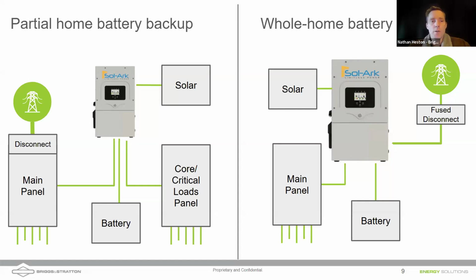So notice on the left side of the screen, if you disconnect from the grid, if you get a power outage, what's going to happen? Well, the inverter is going to isolate its power feed from the main panel, and you're going to essentially have just the battery, the inverter, the solar, and the core loads backed up, in isolation. The difference on the right side of the screen is that the connection to the grid is coming directly from the service entrance. You're going from the service entrance through your disconnect, through your meter, and then your disconnect. And then all of the loads of the house are fed through the inverter. So in a grid outage, the anti-islanding of the inverter will disconnect from grid, and then it'll allow batteries and potentially solar and potentially a generator to continue to feed the loads in the house.